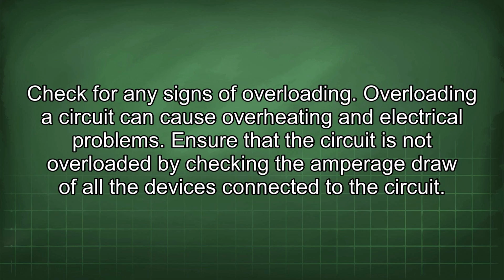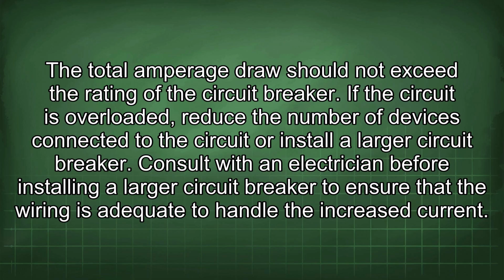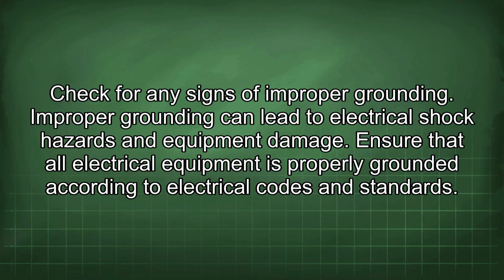Check for any signs of overloading. Overloading a circuit can cause overheating and electrical problems. Ensure that the circuit is not overloaded by checking the amperage draw of all the devices connected to the circuit. The total amperage draw should not exceed the rating of the circuit breaker. If the circuit is overloaded, reduce the number of devices connected to the circuit or install a larger circuit breaker. Consult with an electrician before installing a larger circuit breaker to ensure that the wiring is adequate to handle the increased current.